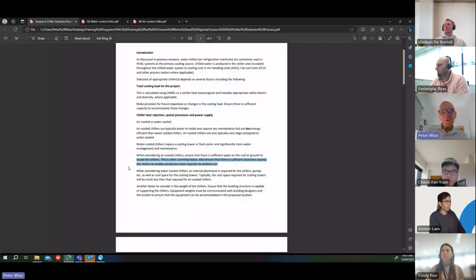Sometimes the building designer or architect will want to hide the chiller in an enclosure on the roof or with walls all around it. So you just need to make sure that you comply with the clearance requirements of the suppliers, and make sure they're going to work satisfactorily. If you're considering water-cooled chillers, an internal plant room is required for the chillers, pumps, etc., as well as roof space for the cooling towers.